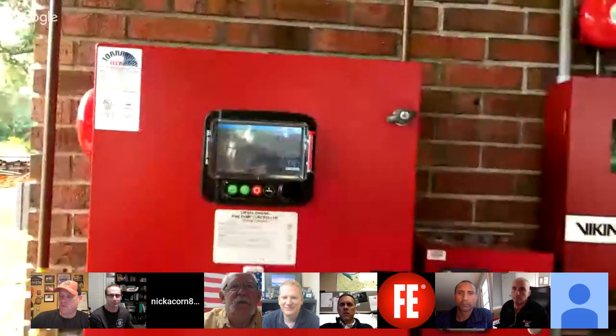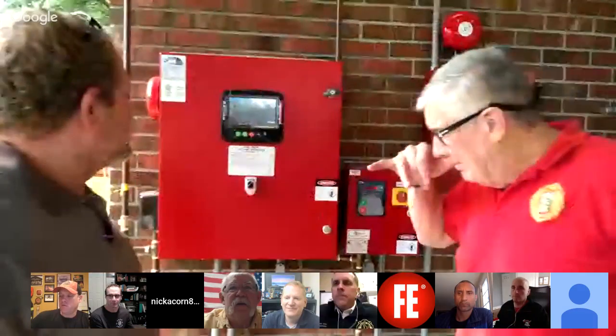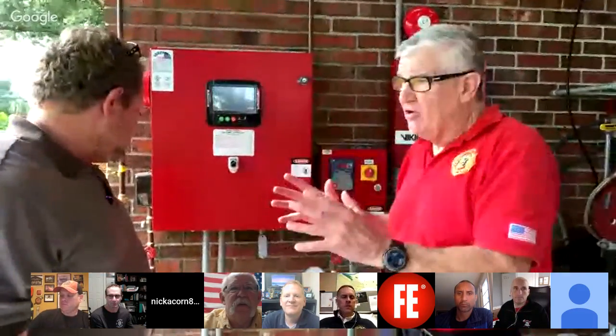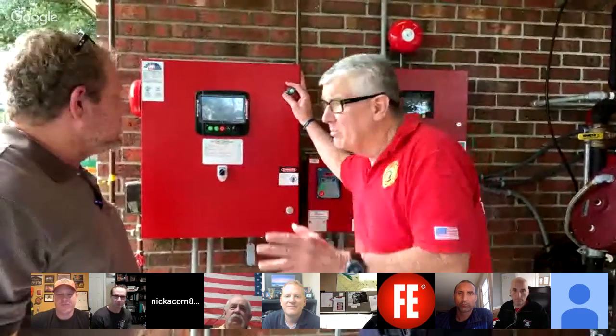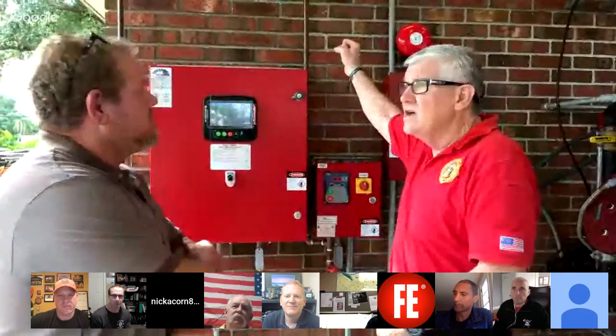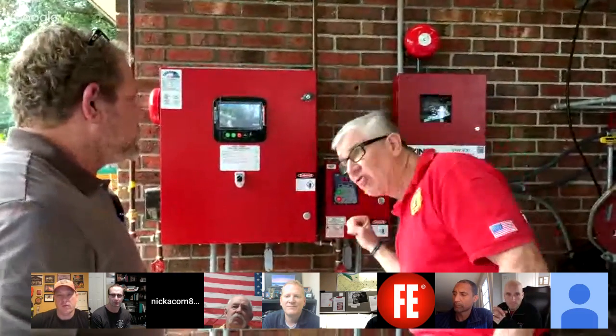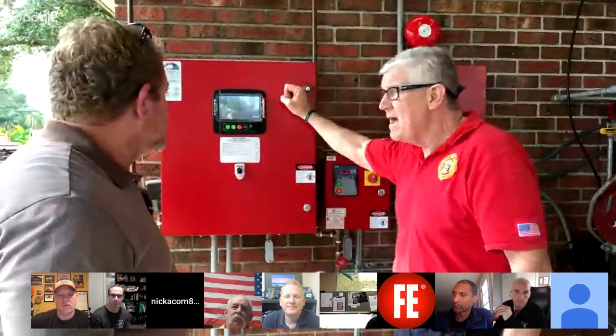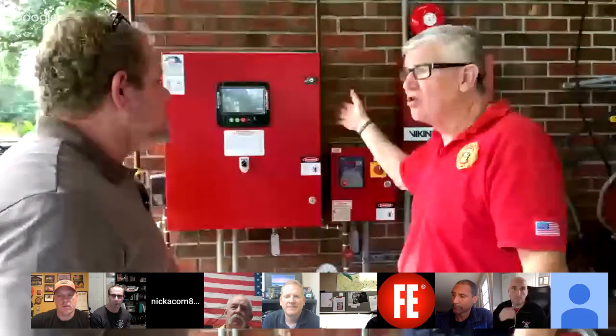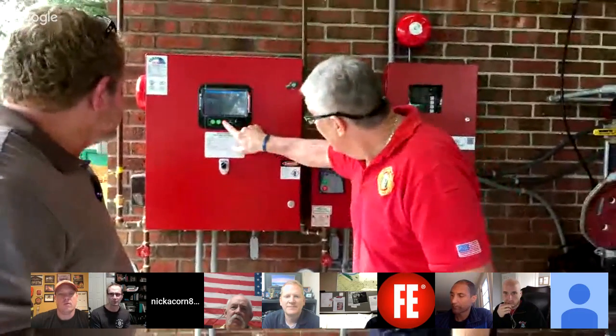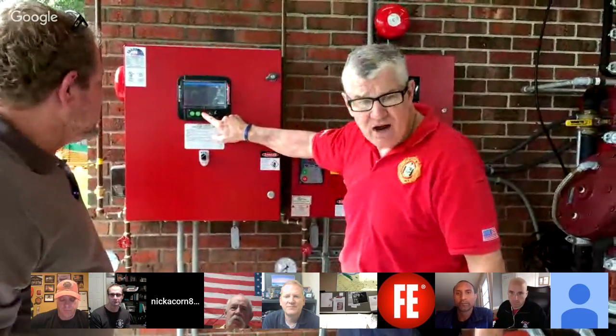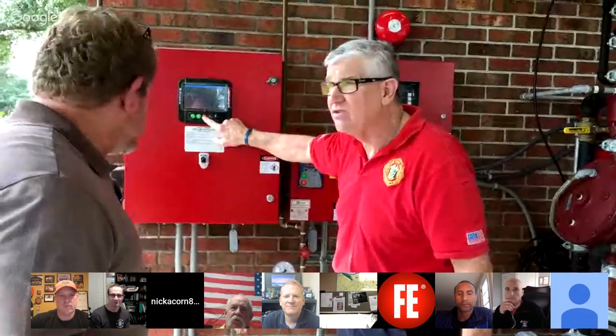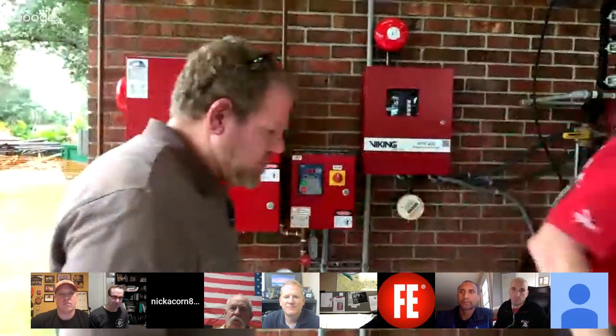That's got a graphic interface for the controller. While I've got you here, we teach in our officer development academy, when we have an electric fire pump controller, that we are to shut off the transfer switch first. Because if we shut off the main disconnect first, then the transfer switch turns on the generator. Okay. But there are times, I understand, and I think I learned this from Kyle Smith, that you can press the red stop button if the demand on the fire pump has been taken away. Okay, understood.